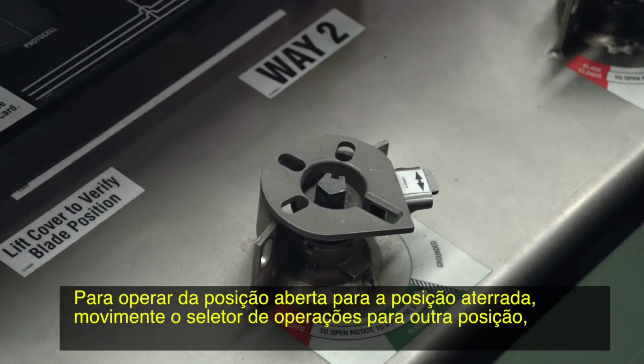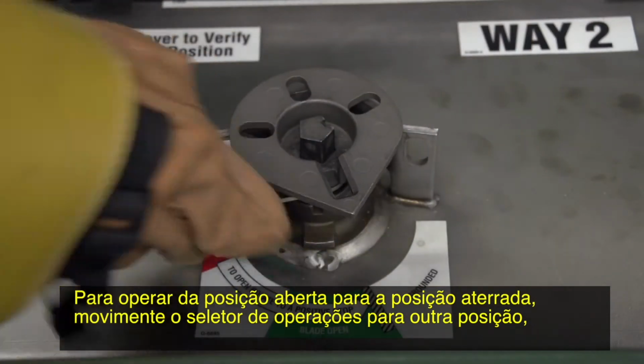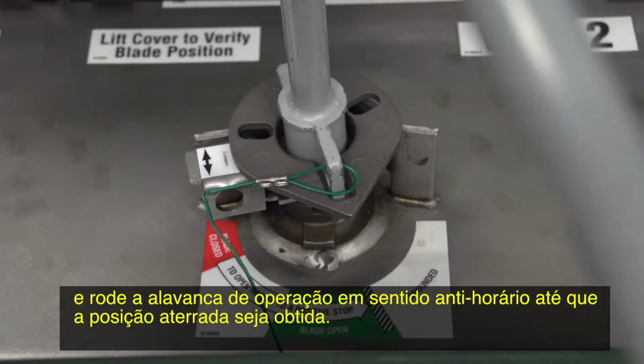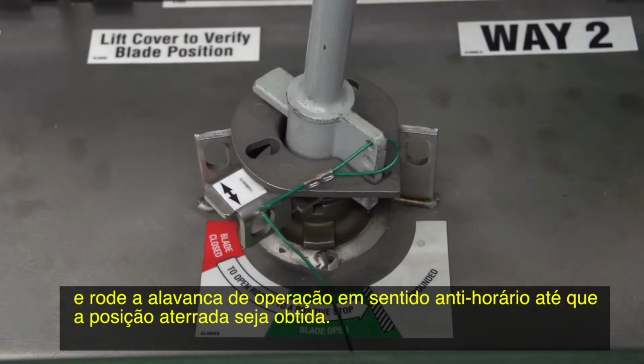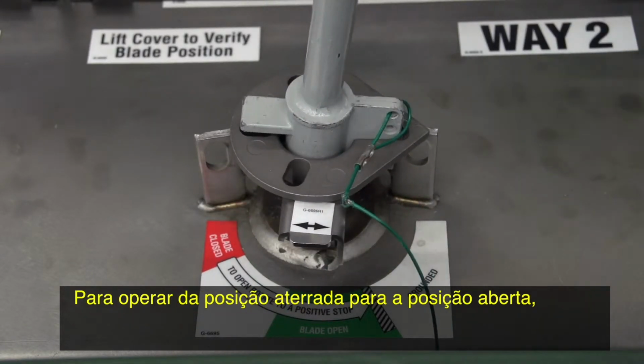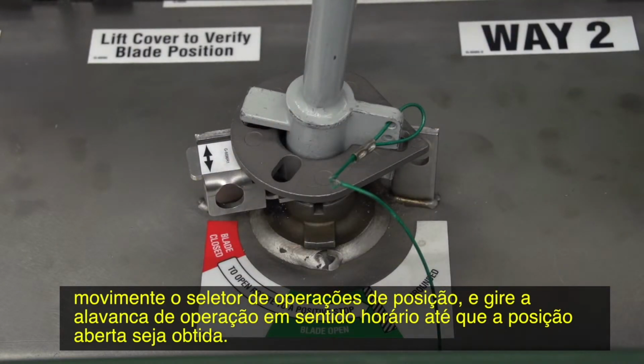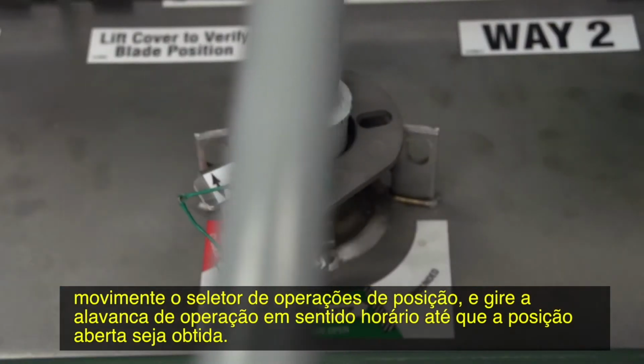To operate from the open to the grounded position, rotate the selector out of the way and rotate the operating handle counterclockwise to a stop in the grounded position. To operate from the grounded to the open position, rotate the selector out of the way and rotate the operating handle clockwise to a stop in the open position. To operate from the open to the closed position, rotate the selector out of the way and rotate the operating handle clockwise to a stop in the closed position. On switches with a 3-pole fault interrupter, the handle cannot be removed until the mechanism is fully charged.